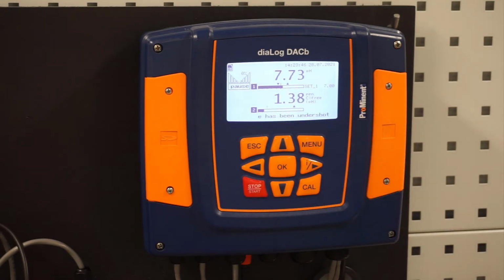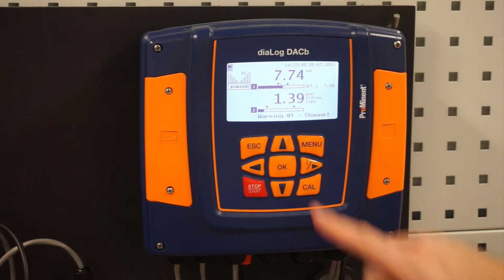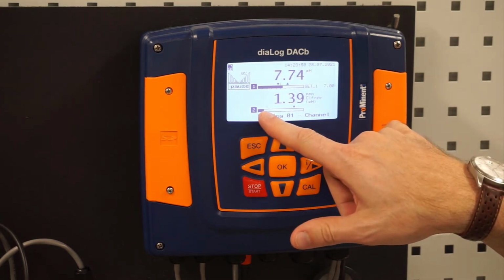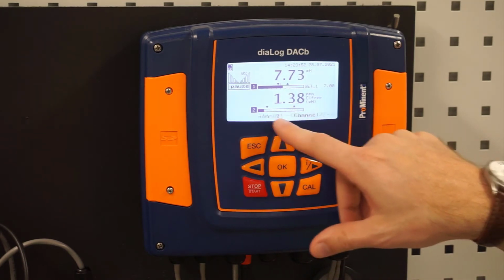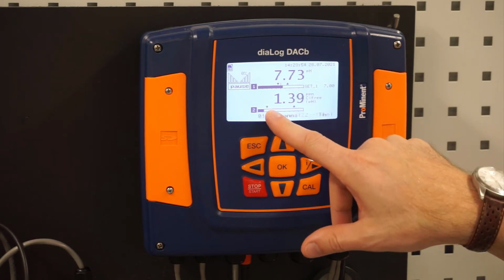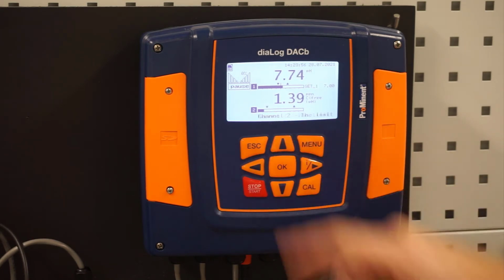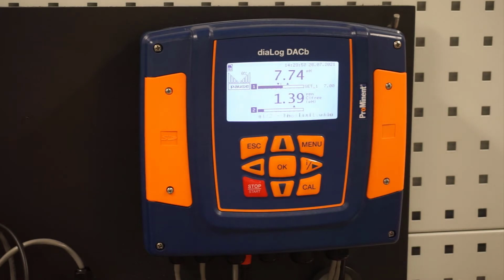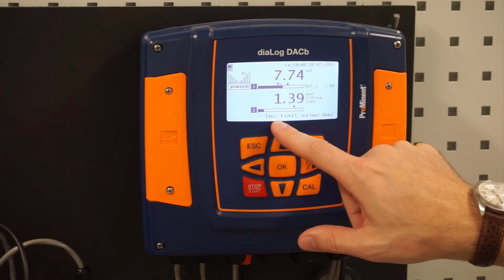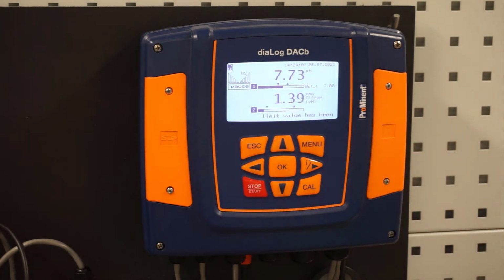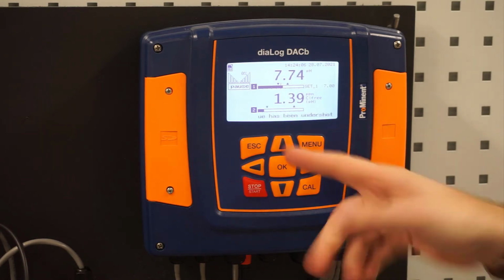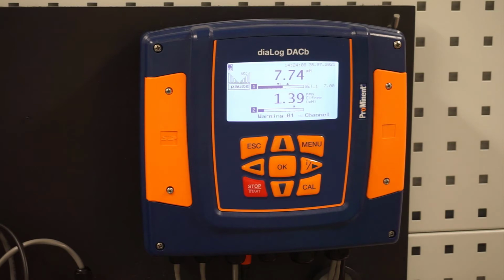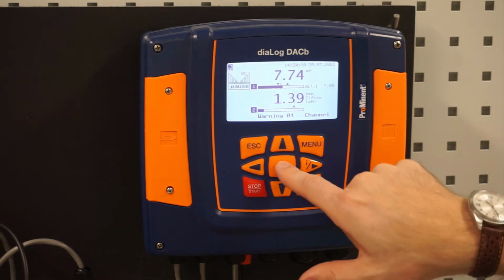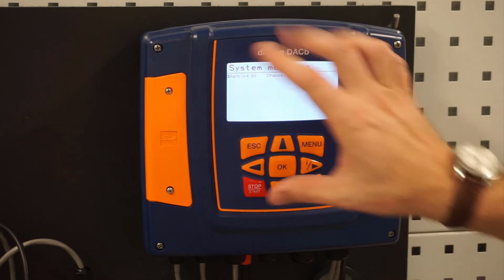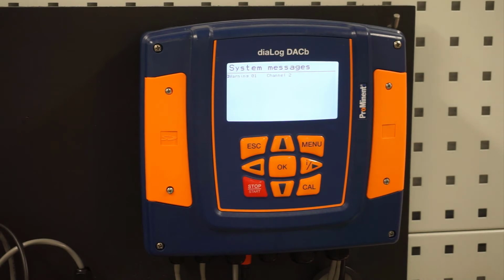Those typically aren't used. I'll show you how to turn those off. You'll notice that our bar here representing our free chlorine is actually below our low limit. You'll notice it is flashing. And then down here scrolling, that actually is telling us what error we have. If you don't want to stand here and read it as it's going by, if I hit the OK key, it's going to bring up all my list of warnings.